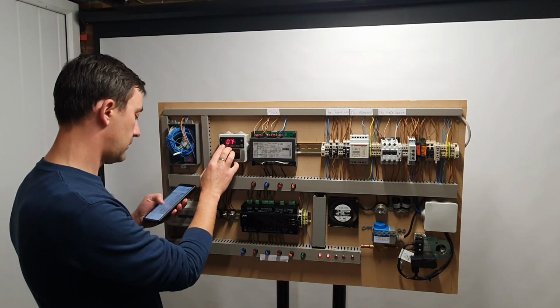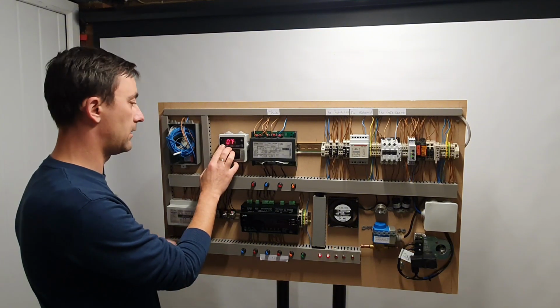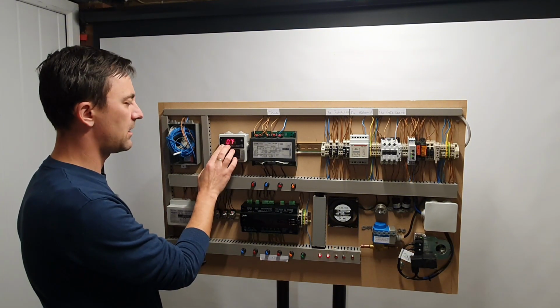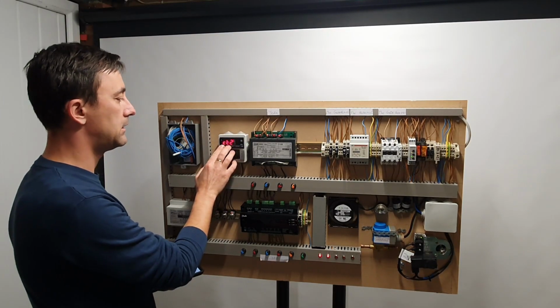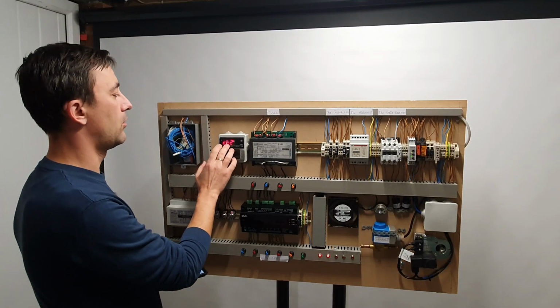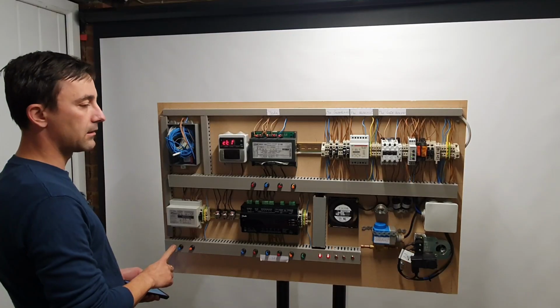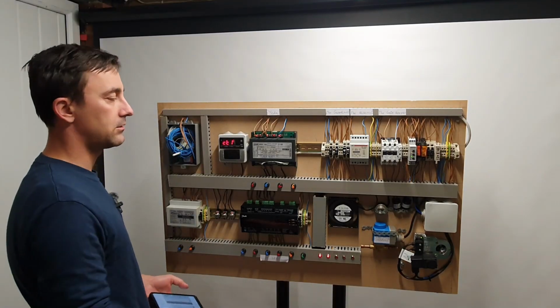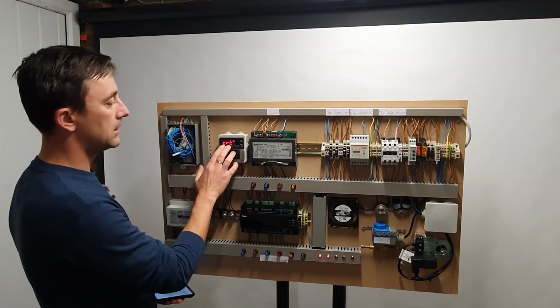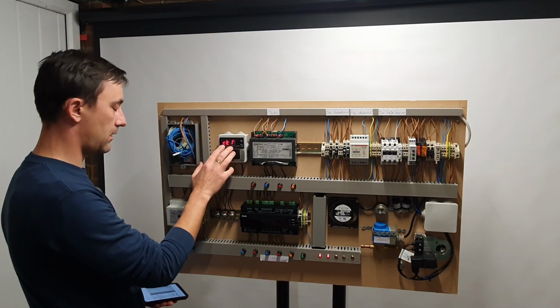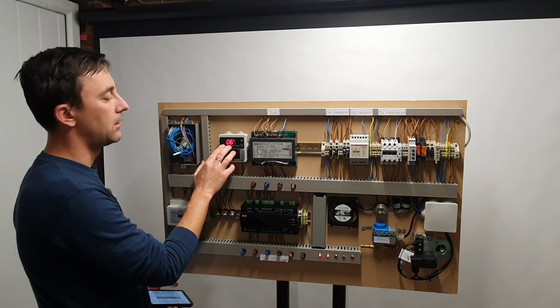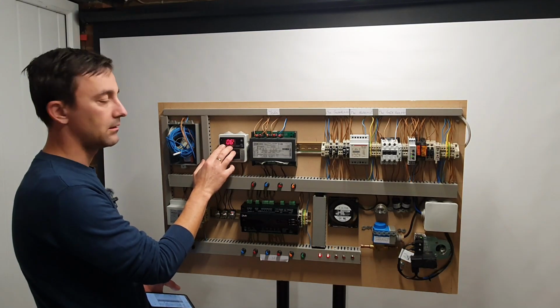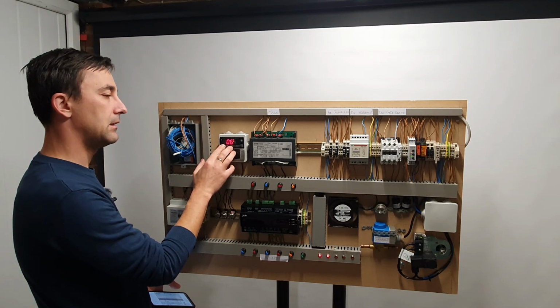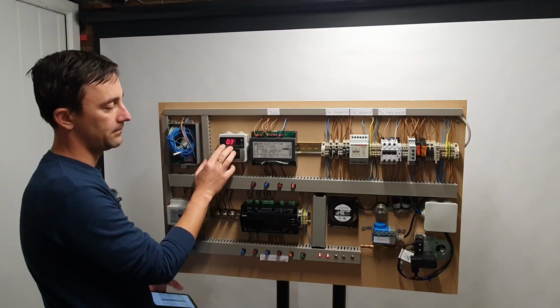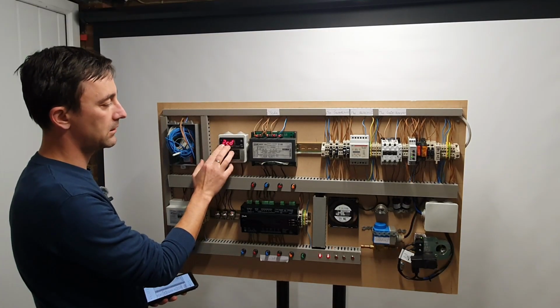CT1 is compressor run with T1 failure. So 7 minutes. I would put this to maybe 6 minutes. CT2 3 minutes. So if we have an air probe failure, we still want the system to work until an engineer attends site. So what you're going to tell the controller is basically, if the probe fails, you run the compressor no matter what for 6 minutes, and then you stop and you rest for 3 minutes, and then you repeat the same process again. So these are these two parameters.